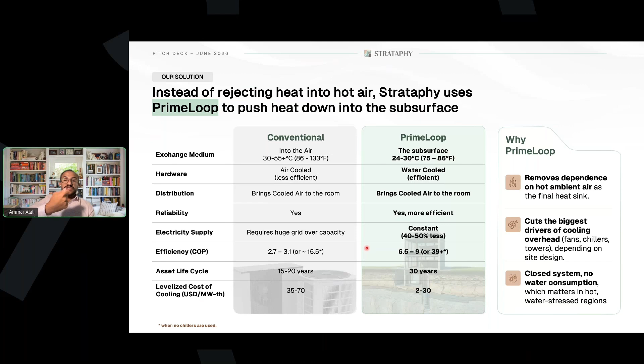Electricity supply is key. Most data centers are away from the cities, and whenever they're built, they need to have their own substation. Substation and grid connection are extremely expensive. So any improvement on the total load, the peak load at any point of the year, reduces your initial investment in the substation, ultimately reducing your capex to build the facility. The golden metric we like to talk about all the time is the coefficient of performance, which is the electricity consumption for whatever thermal exchange load you have.